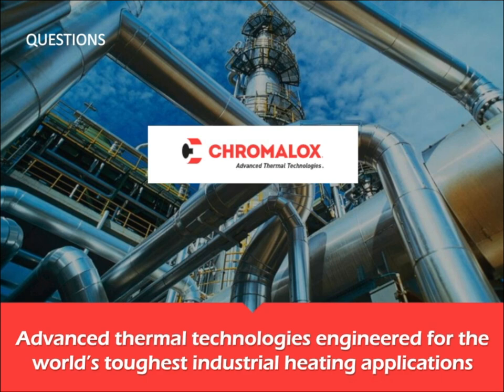Okay, great. We've got time for one more question here. Considering that these heaters are large kW heaters, is harmonic distortion an issue with these large heating systems? Sure. For electrical people that are on the line, we do get that question about harmonic distortions, and that has to do with the power switching. The one thing to keep in mind is there's really two different power switching modes we talked about. There's a zero cross, which is what we use for our typical application, and you're not going to have the harmonic distortions during operation.